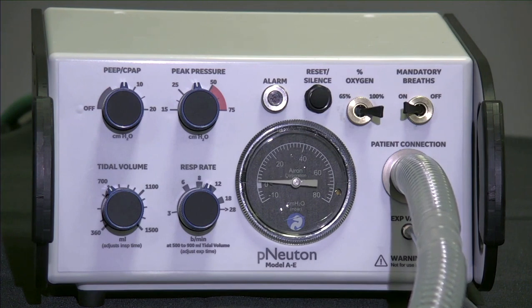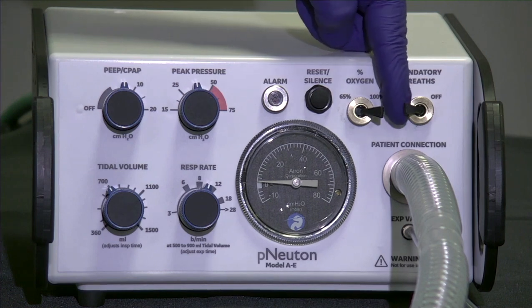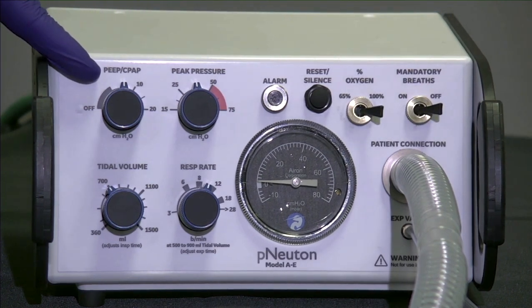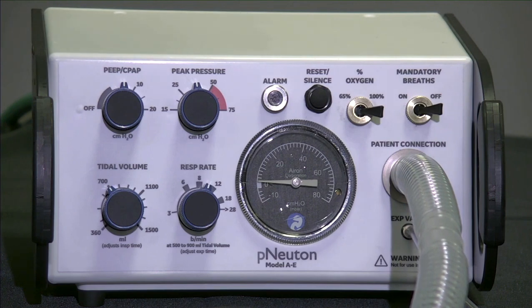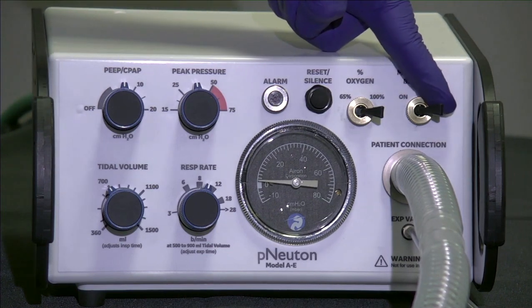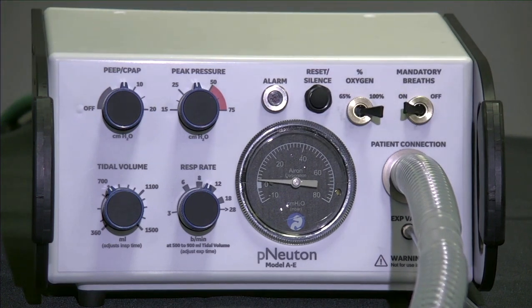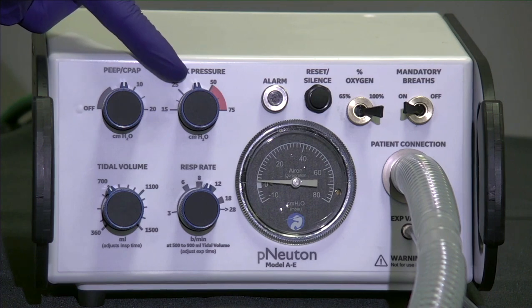Let's look at the operation for the CPAP system. For a spontaneously breathing patient, we can turn the mandatory breaths to off and adjust the CPAP to the desired level. As you can see, the CPAP system is very responsive with very low work of breathing. The integrated CPAP PEEP supports the IMV mode by turning the mandatory breaths to on. You can also ventilate in pressure limit mode. The peak pressure control can be used to pressure limit breaths for pressure ventilation.